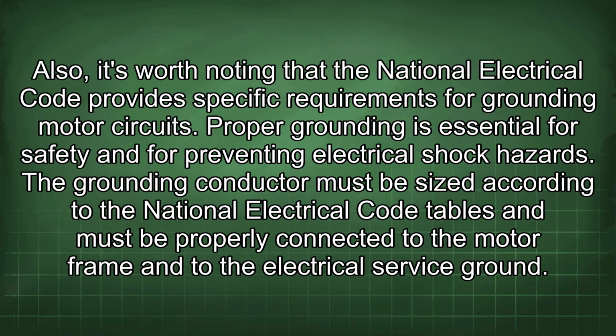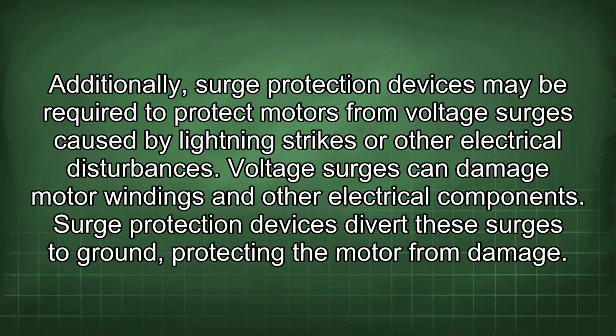Also, it's worth noting that the National Electrical Code provides specific requirements for grounding motor circuits. Proper grounding is essential for safety and for preventing electrical shock hazards. The grounding conductor must be sized according to the National Electrical Code tables and must be properly connected to the motor frame and to the electrical service ground. Additionally, surge protection devices may be required to protect motors from voltage surges caused by lightning strikes or other electrical disturbances. Voltage surges can damage motor windings and other electrical components. Surge protection devices divert these surges to ground, protecting the motor from damage.